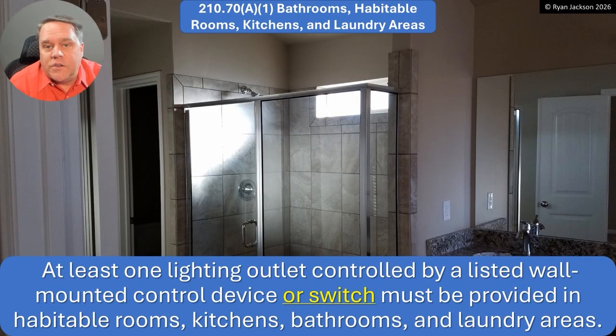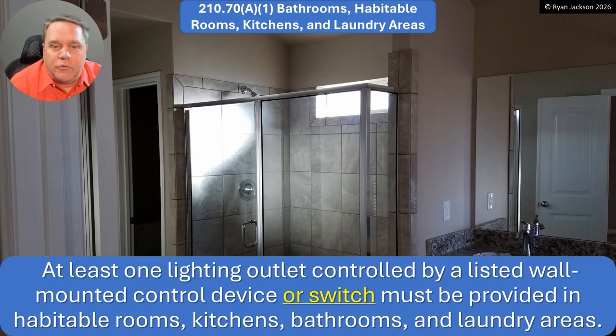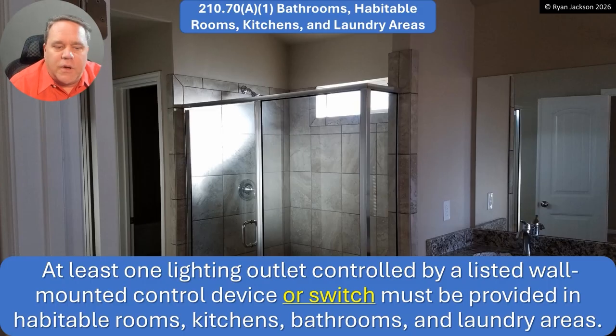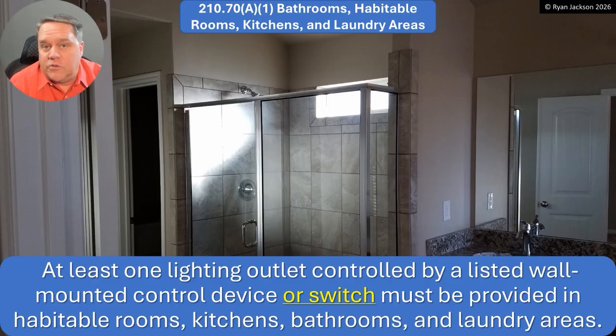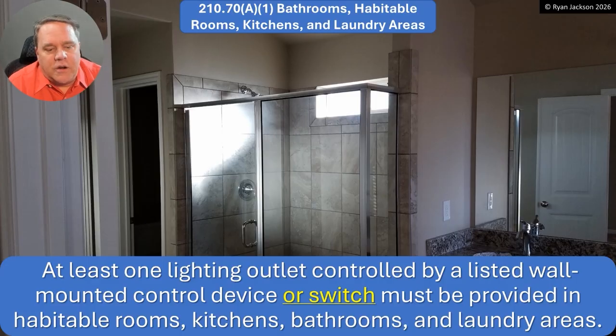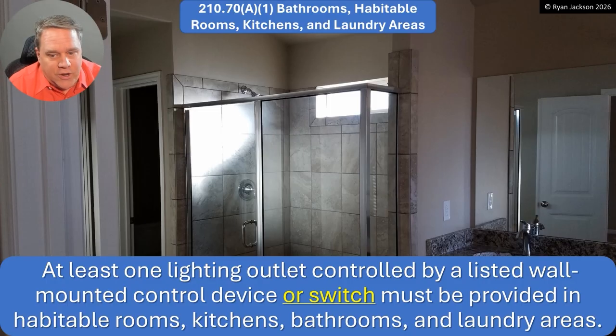A1 talks about your bathrooms, habitable rooms, kitchens, and laundry areas. At least one lighting outlet controlled by a listed wall-mounted control device or switch must be provided in habitable rooms, kitchens, bathrooms, and laundry areas.